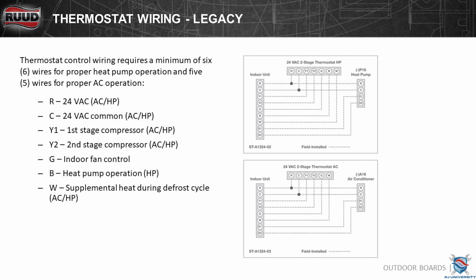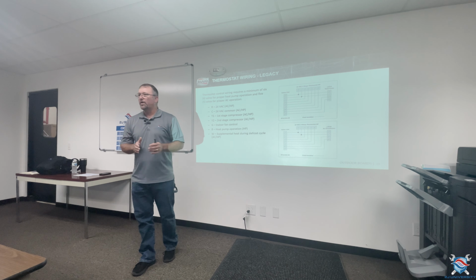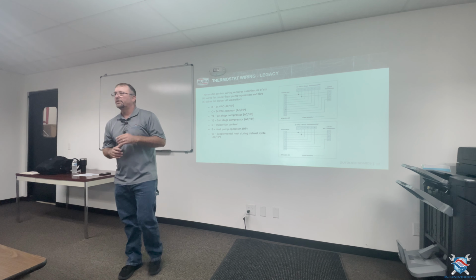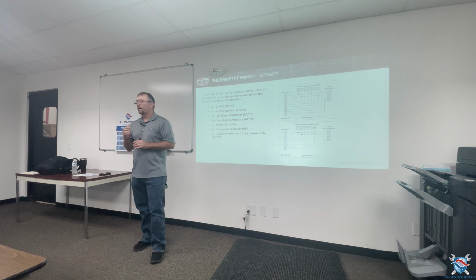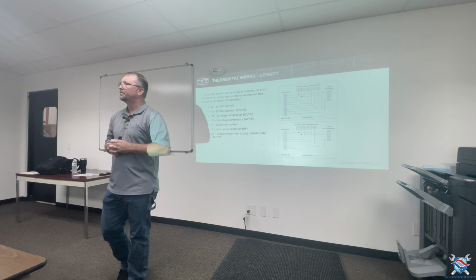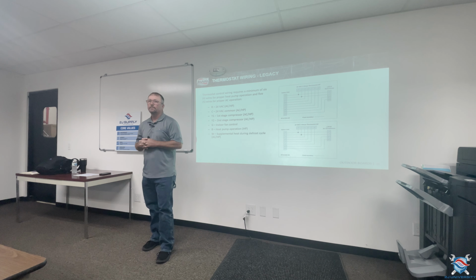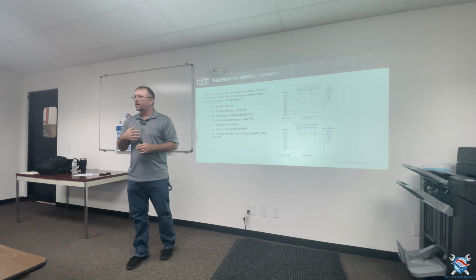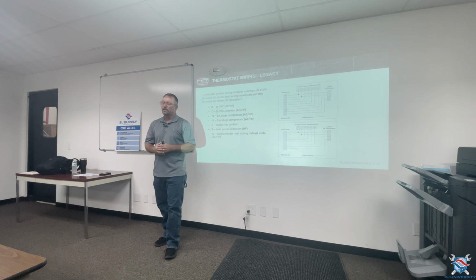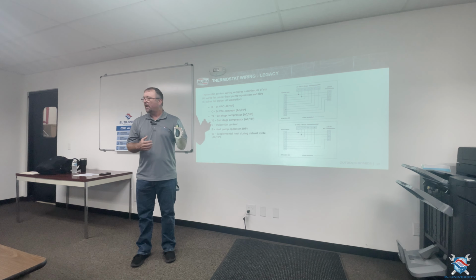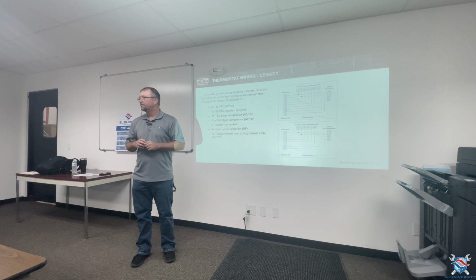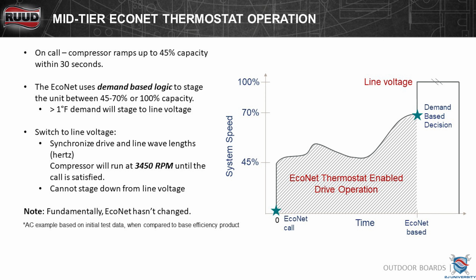So let's get into that just a little bit. I have a 3-year-old furnace that I want to put a UA15 on, and it's not a Rheem furnace, and I'm going to try to use an RA15. Can I do it? Nope. Can't put it on there because it doesn't have the 4-wire EcoNet connectivity to it. I'm telling you this because I want you to be very cautious when you're trying to sell these things, install them, or service them. If I don't have an EcoNet compatible indoor unit, I cannot put these units with that indoor. It has to be compatible.